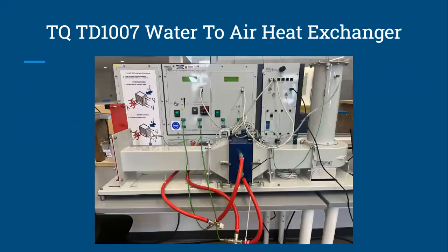So here's the machine used to test these heat exchangers. It is called the TQ-TD1007 water to air heat exchanger. And to set up this machine, we first place the heat exchanger right here in the middle between these two steel frames, and then we clamp it down using these clamps here. Then we'll connect the pipes. The bottom one here is the water supply, and the top one's the water return.